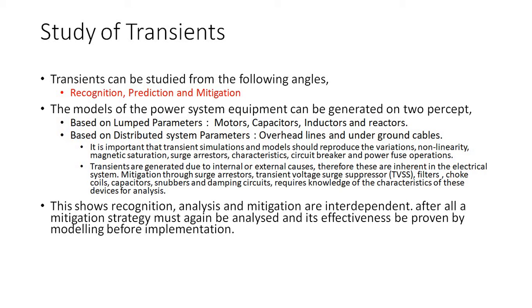Transients are generated due to internal or external causes. Therefore, these are inherent in the electrical system. Mitigation through surge arresters, transient voltage surge suppressors, filters, choke coils, capacitors, snubbers and damping circuits requires knowledge of the characteristics of these devices for analysis. This shows recognition, analysis and mitigation are interdependent. After all, the mitigation strategy must again be analyzed and its effectiveness proven by modeling before implementation. Thank you.